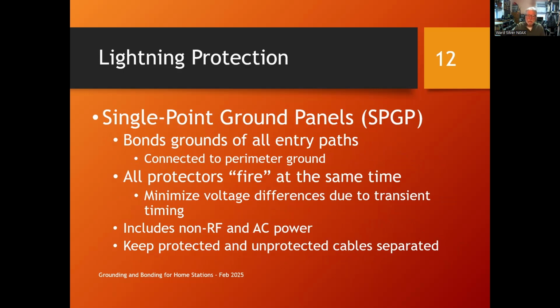Okay, there's that term, single point. We're going to see a drawing of this in a minute. To help the lightning get to where it wants to go, with a minimum of flowing through your house and your station, you use a single point ground panel or an SPGP. The idea is all of the entry paths from the cables that come from outside the station, they all go to this same panel. And it bonds the grounds of all those entry paths.